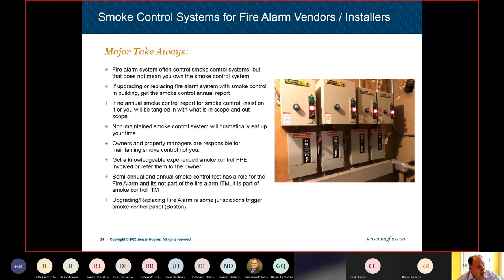The semi-annual and annual smoke control test has a role for the fire alarm, and it's not, like I said, part of the fire alarm ITM. It's part of the smoke control inspection, testing, and maintenance. Some people try to throw it all in or say everything's owned, but NFPA 72 requirements for ITM do not include these smoke control end-to-end tests. It's an important piece, and we certainly need the fire alarm service companies involved to make it all happen, because they're an integral piece of that.